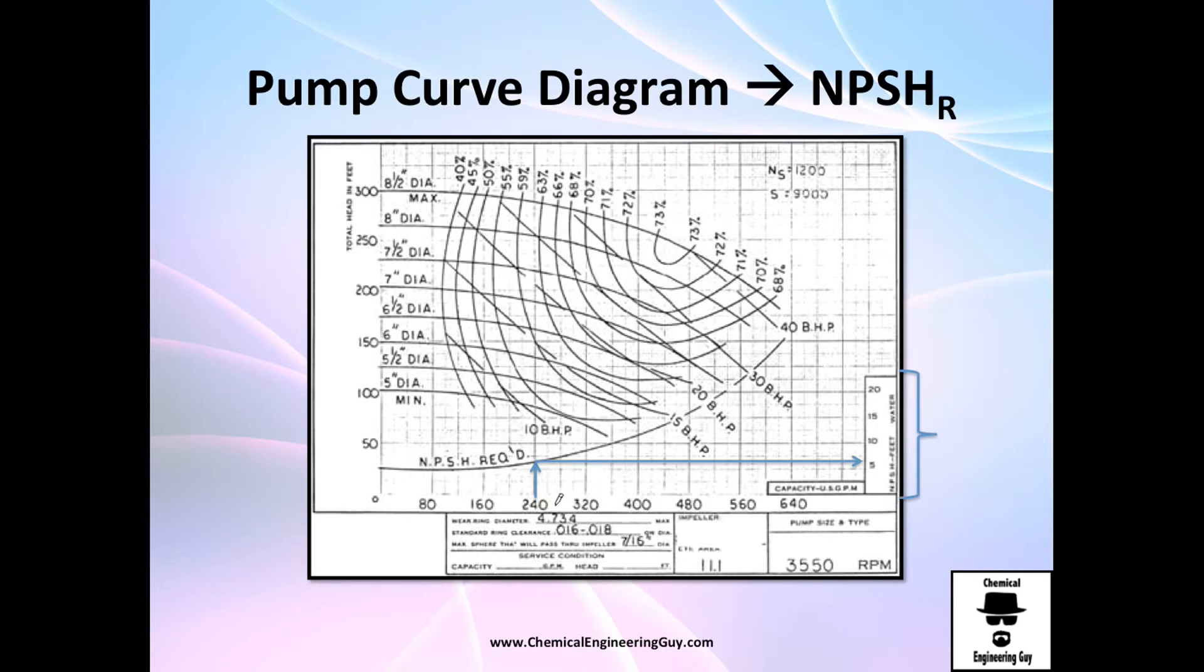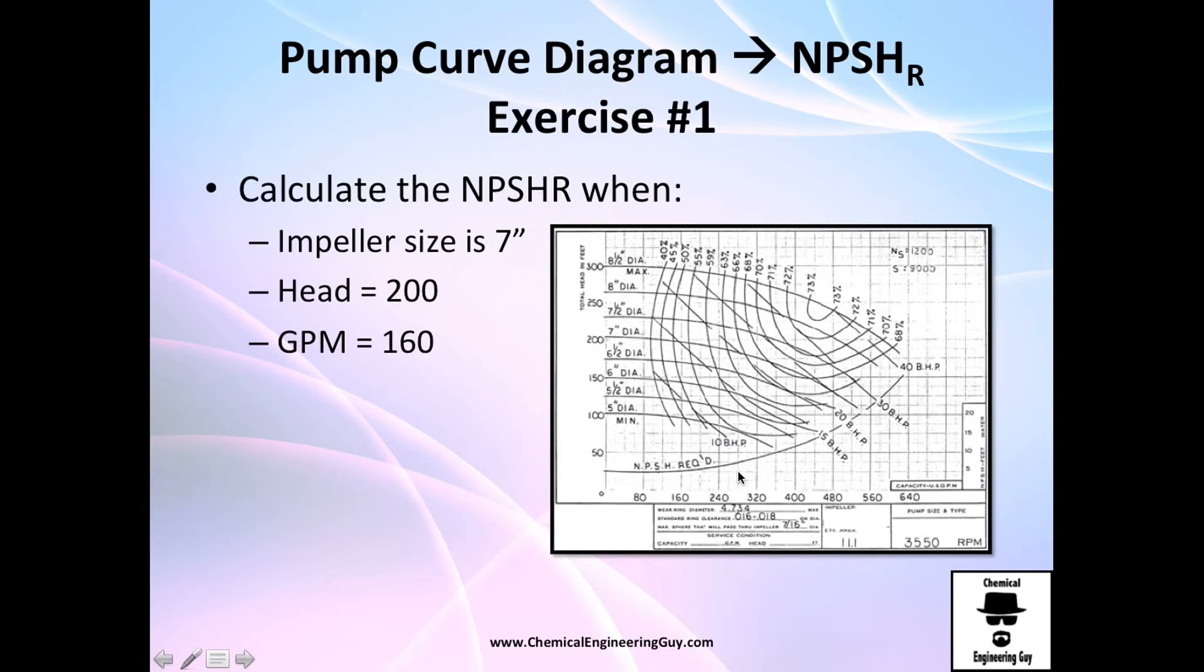Let's see what's the NPSH R. I will operate with 240 gallons per minute. I intersect this and go directly to the right and find it to be 5 or something around 5. For 480, intersect with this line and go to the right, and my NPSH R must be 15. We're going to do a pretty cool exercise in which we go backwards.